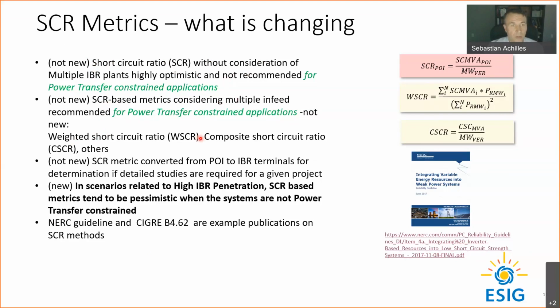Weighted short circuit ratio, composite short circuit ratio, there are others. Here I mentioned a NERC reliability guideline. There's also a CIGRE brochure 62... publication, and several other brochures related to short circuit ratios that consider in-feed. Those are the ones recommended, and they calculate short circuit ratios that represent how weak an area is, not how weak a single project is.